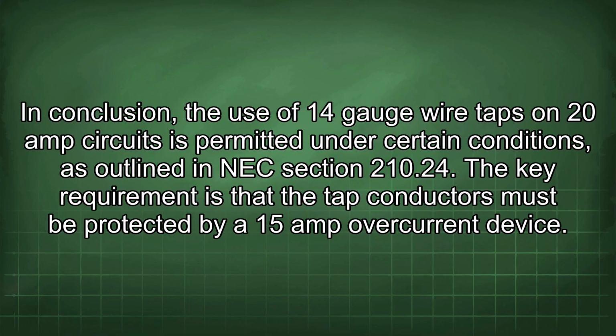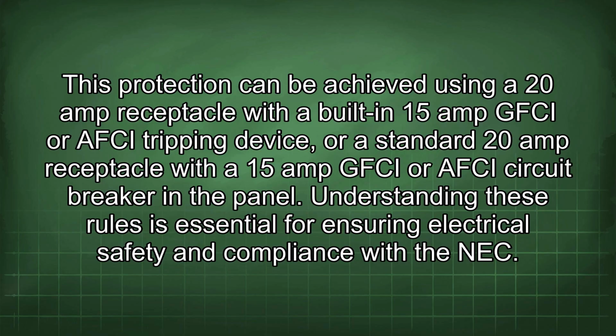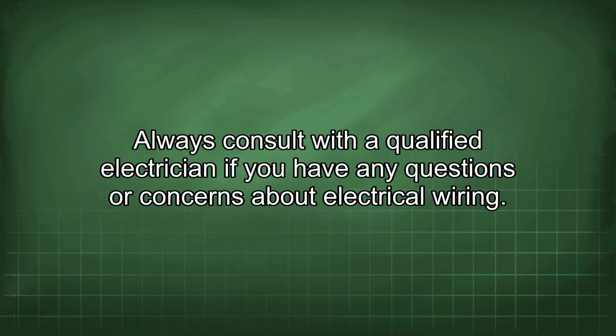In conclusion, the use of 14-gauge wire taps on 20-amp circuits is permitted under certain conditions, as outlined in NEC section 210.24. The key requirement is that the tap conductors must be protected by a 15-amp overcurrent device. This protection can be achieved using a 20-amp receptacle with a built-in 15-amp GFCI or AFCI tripping device, or a standard 20-amp receptacle with a 15-amp GFCI or AFCI circuit breaker in the panel. Understanding these rules is essential for ensuring electrical safety and compliance with the NEC. Always consult with a qualified electrician if you have any questions or concerns about electrical wiring.